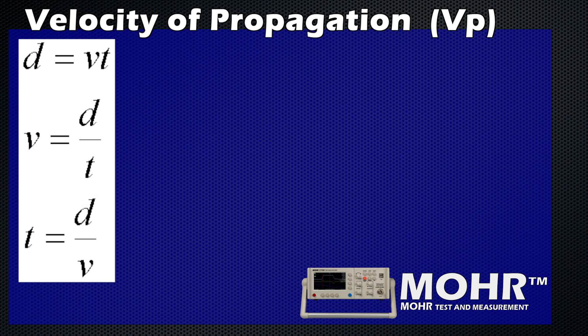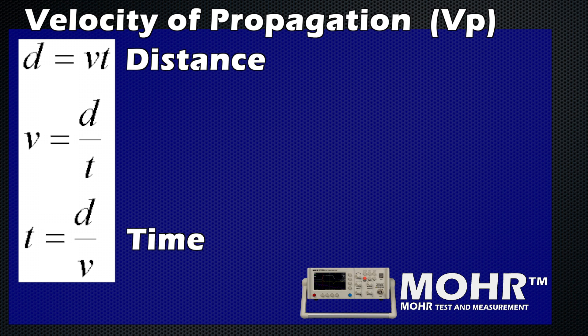An important note: a TDR measures in time — the time it takes to get to the measurement and back. And this is how we come up with the equation of distance over time equals velocity of propagation, or VP equals D over T.